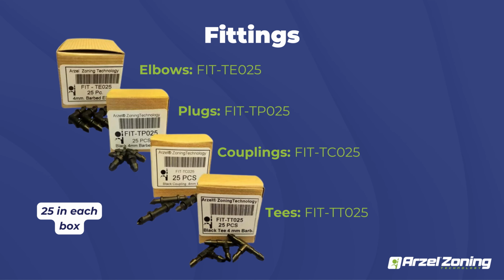The next one up is our couplings. You guys won't really need them a whole lot unless you cut your tubing too short, or if you want to add dampers later on down the line. We have those available as well. The next one up is going to be our plugs. The plugs themselves, if you guys are service technicians, I would definitely have these on the truck. If you ever come across a leaking damper or something in our system, it just speeds up that troubleshooting time. And we do offer specific trainings on troubleshooting the pneumatic side of the dampers as well.